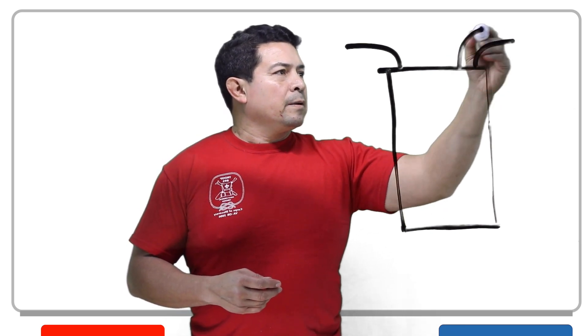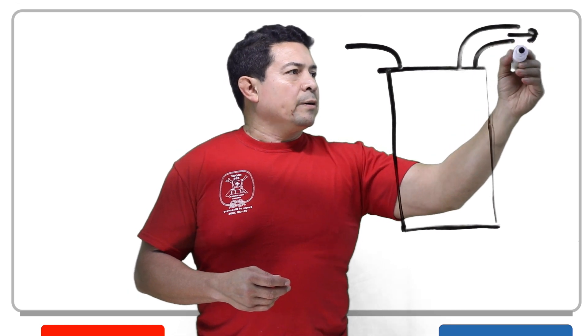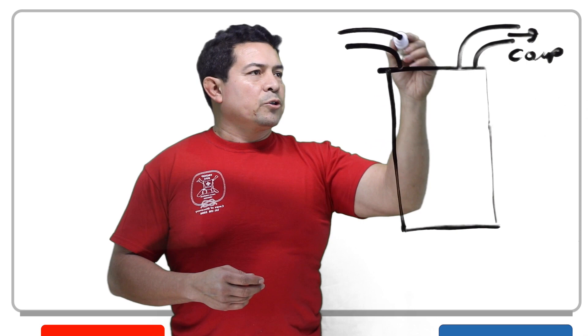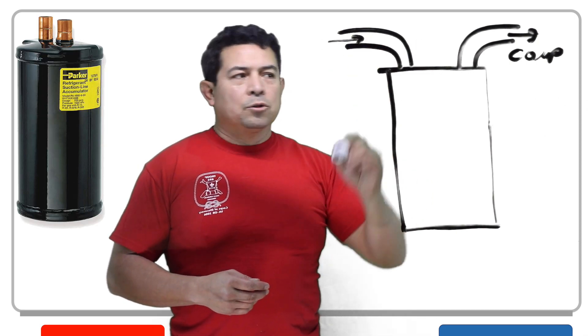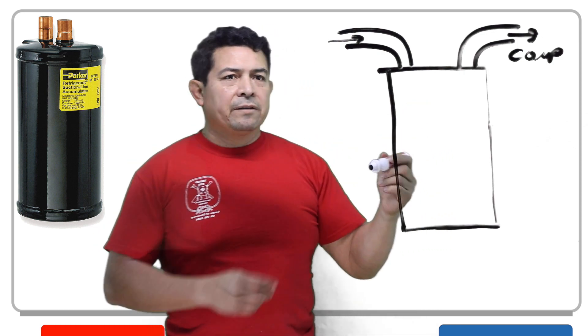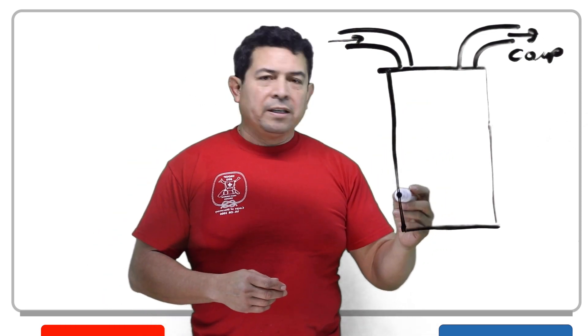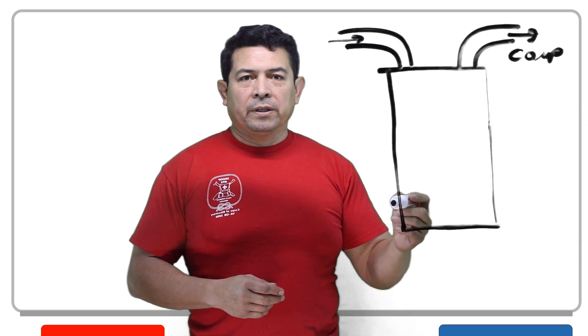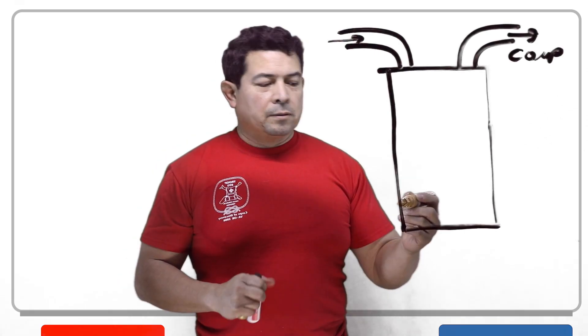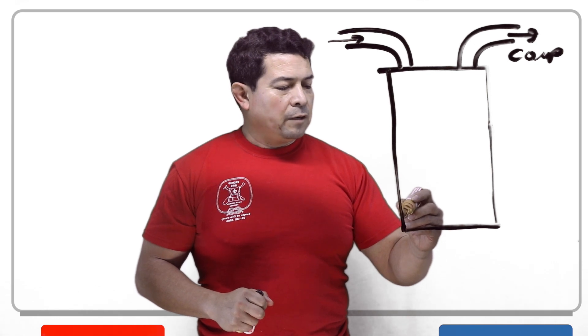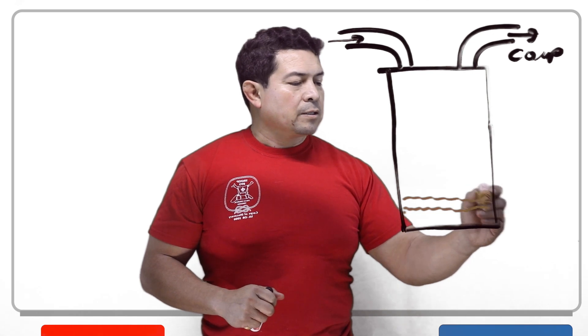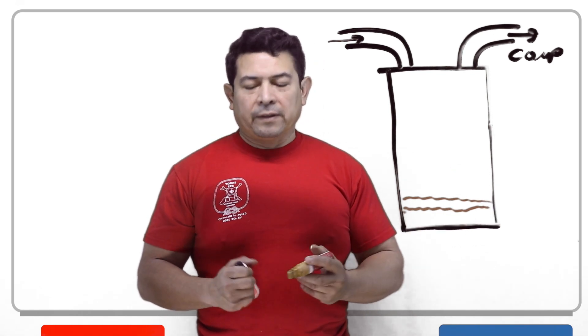Refrigerant is going to be going out to the compressor and refrigerant is going to be coming in to the accumulator here. But what happens is, inside of it, they have re-piped it so that if there is liquid refrigerant coming back, it's going to sit at the bottom of the accumulator along with any oil that might be trapped — it's going to be held right there.